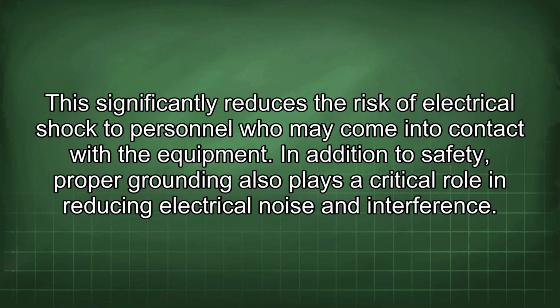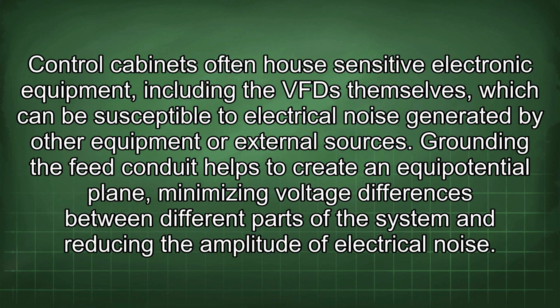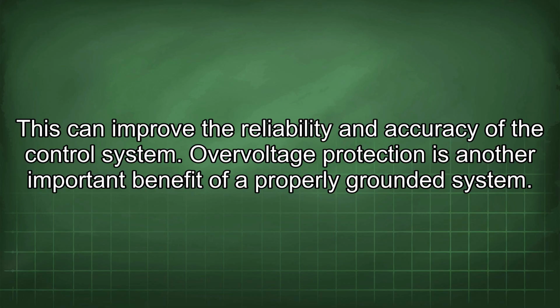In addition to safety, proper grounding also plays a critical role in reducing electrical noise and interference. Control cabinets often house sensitive electronic equipment, including the VFDs themselves, which can be susceptible to electrical noise generated by other equipment or external sources. Grounding the feed conduit helps to create an equipotential plane, minimizing voltage differences between different parts of the system and reducing the amplitude of electrical noise. This can improve the reliability and accuracy of the control system.